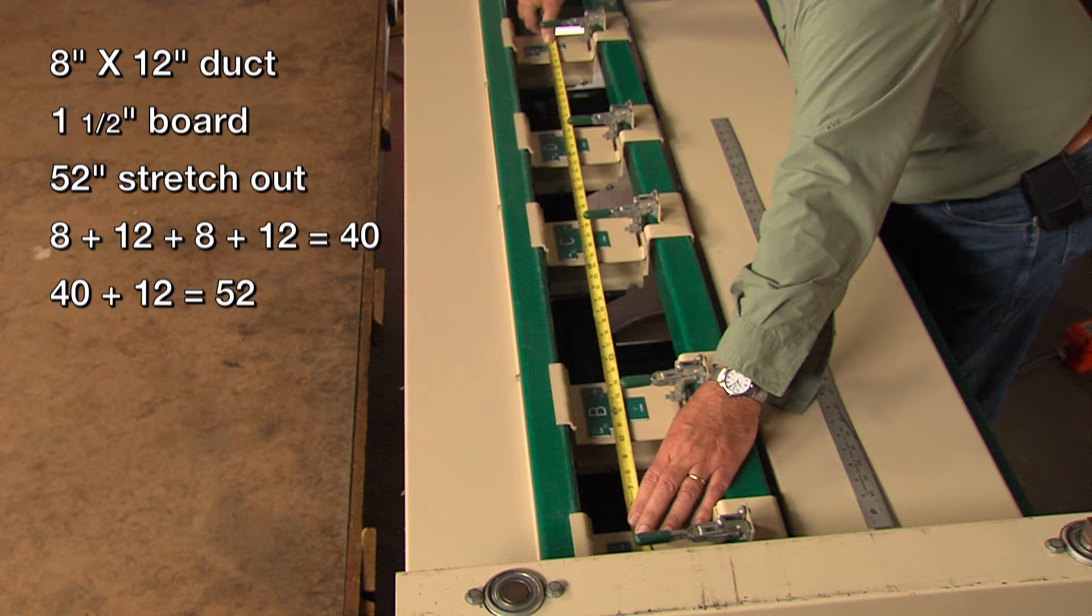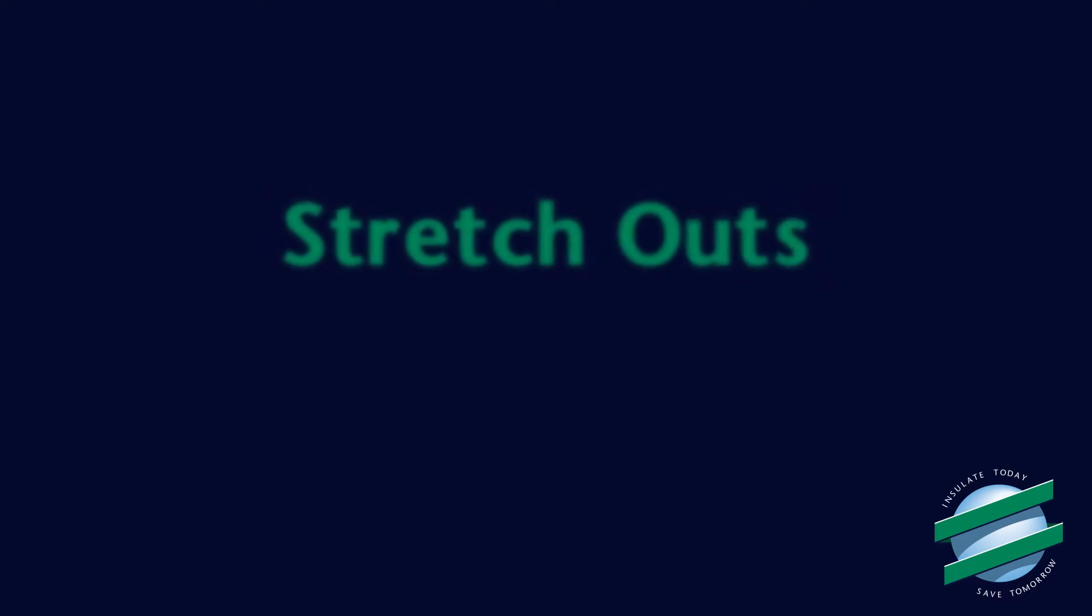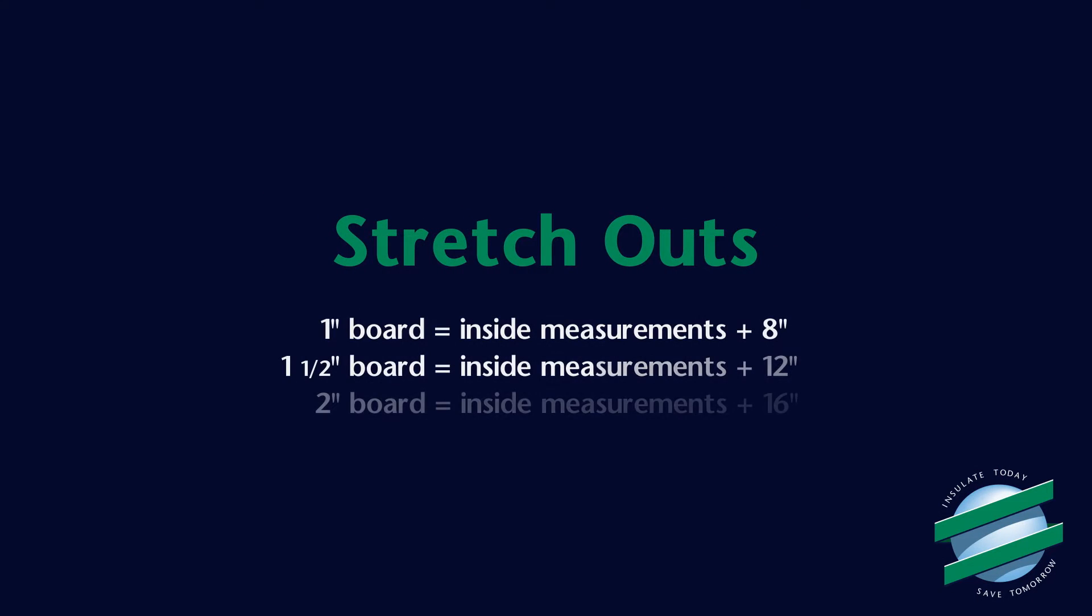For your information, the stretch out on one inch board is inside measurements plus 8 inches, one and a half inch board is inside measurements plus 12 inches, and two inch board is inside measurements plus 16 inches.